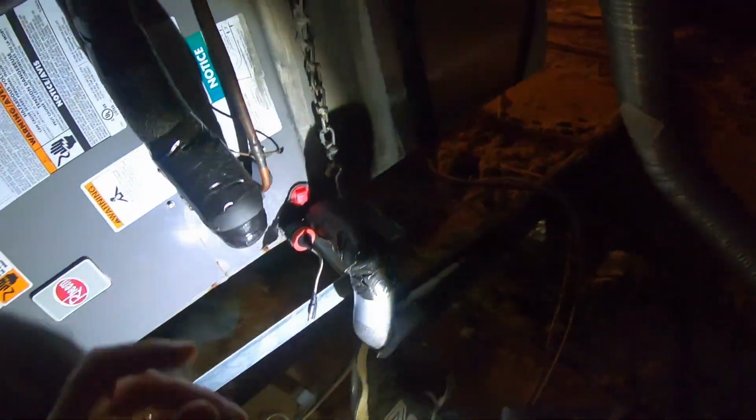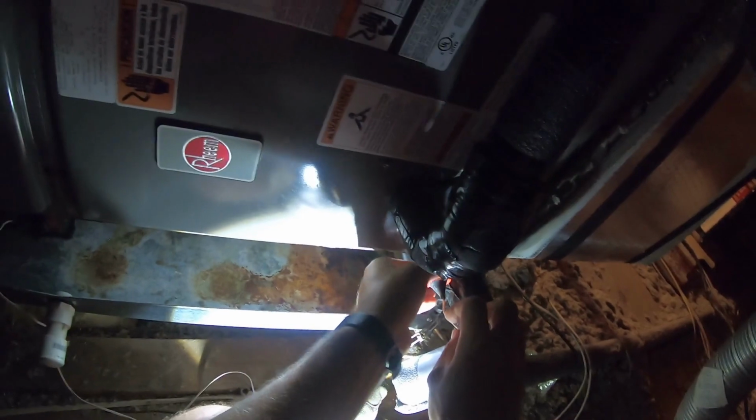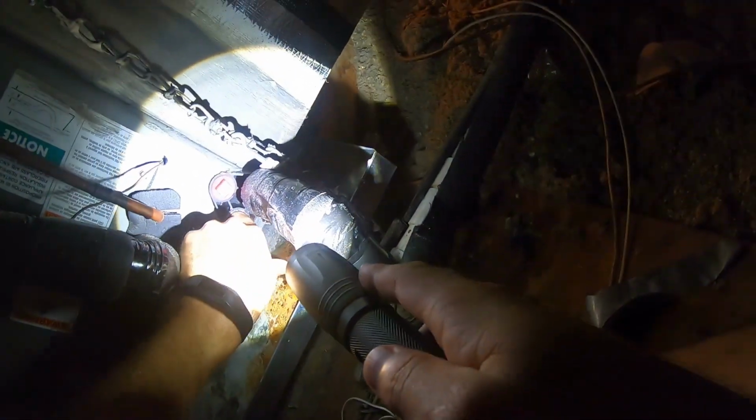Now we're going to unscrew this right here. I think it's going to be a two-handed operation. The fitting's coming out too. Actually, we'll just take the whole thing out. Be able to get the pan tablets in there better. Now you really should take this whole cover off and clean the pan out that way. It's just a lot of work. This one actually isn't that bad anyway. I'm rooting around in there. A little bit of water, but not too much. Not too much snot. And it's the snot that we worry about, not the water.